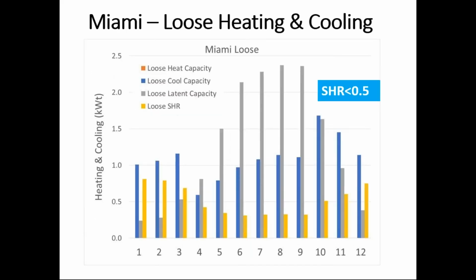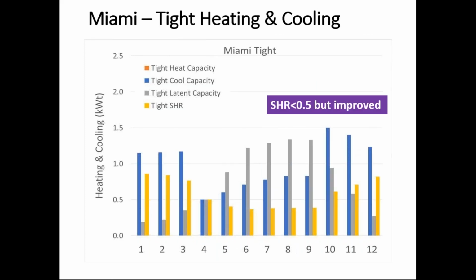Now, when we look at the heating and cooling loads, Miami doesn't have a heating load, so there's no orange bars on that. In our report on overall house characteristics, when we look at some other locations, we do have the heating season as well as the moisture, the humidification needs. In the case of Miami, we're dehumidifying all year, and the latent capacity peaks in the summer, and it's much greater in this loosely sealed home than the sensible cooling, the blue bars, and that gives us a sensible heat ratio that's much less than 0.5. So this home, definitely to maintain comfort, you're going to add a dehumidifier on top of the other conditioning equipment.